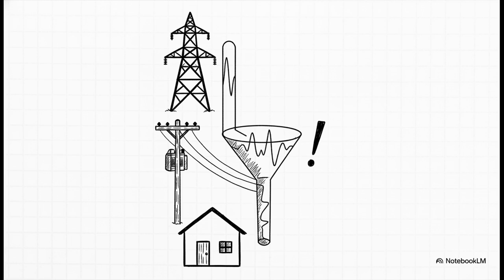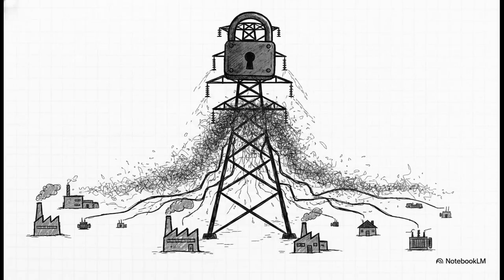Now here is a massive, counterintuitive twist that catches a lot of people off guard. As the voltage drops, the THD limits actually get looser. Yeah, it's literally the exact opposite of what most of us instinctively assume. Usually, you'd think regulations get stricter the closer you get to the end consumer, right? But here, the lowest voltage actually gets the highest allowance for distortion. So why on earth are the rules written this way?